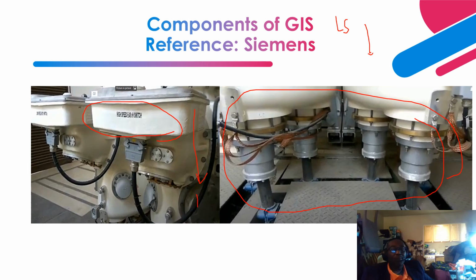Okay, then sometimes if you have an overvoltage condition or basically a fault in a component or a module, you have high-speed earthing switches that basically take the energy to ground to prevent the energy from cascading into other components. And usually a lot of times this is basically the external interface.